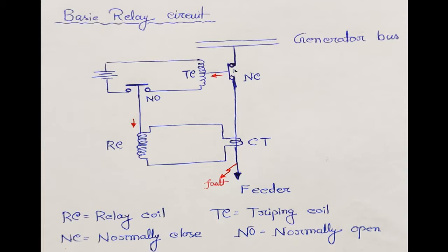As this switch is closed, in the normal healthy condition, when there is no fault in the power system, power is able to flow from the generator bus to the load through this feeder because this switch is normally closed. And one CT is also connected here, and the secondary of the CT is connected to one of the coils. The name of the coil is relay coil. RC means relay coil.